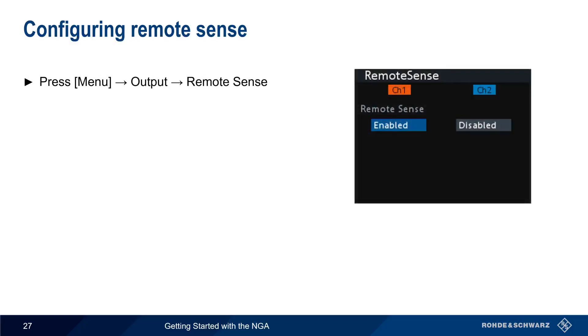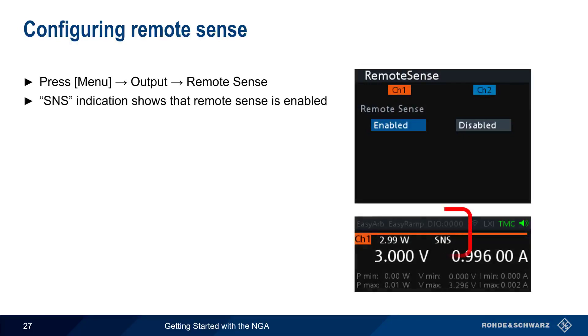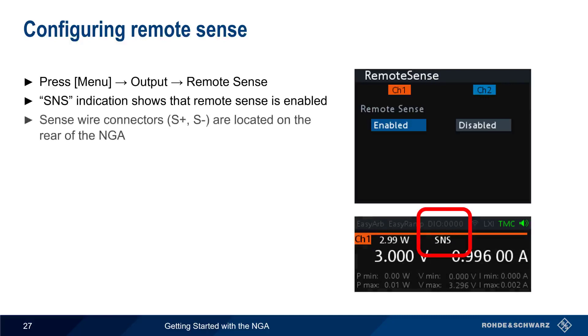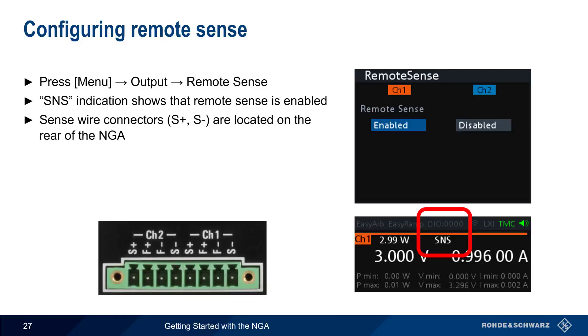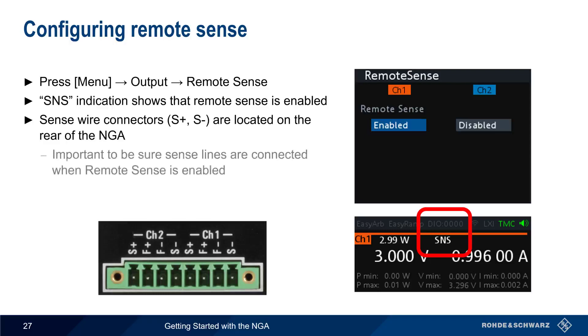To configure remote sense, press the menu hard key and then select output remote sense. If remote sense is enabled for a channel, this is indicated by SNS in the display. The sense wire connectors, S-plus and S-minus, are located on the rear of the NGA. It's important to be sure that the sense lines are connected when remote sense is enabled; otherwise, erroneous voltage and current levels may result.